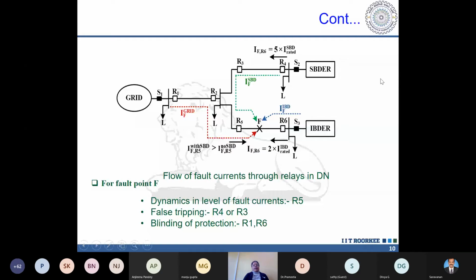So now for fault point F, can you say why the dynamics occur? The first issue was dynamics in fault current, the second was direction change in fault current, the third was false tripping, and the fourth was blinding of protection. So for this fault point F, the dynamics in fault current change.